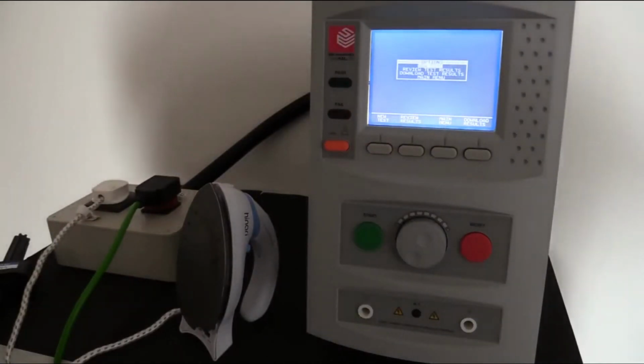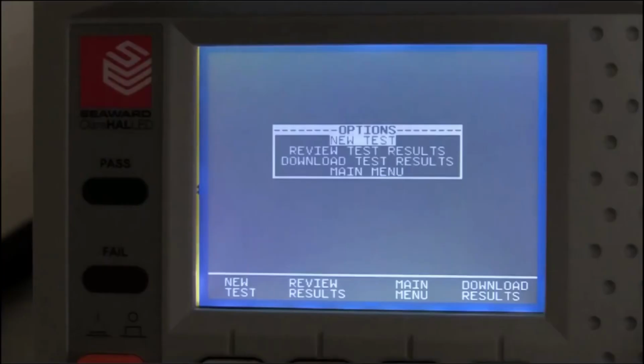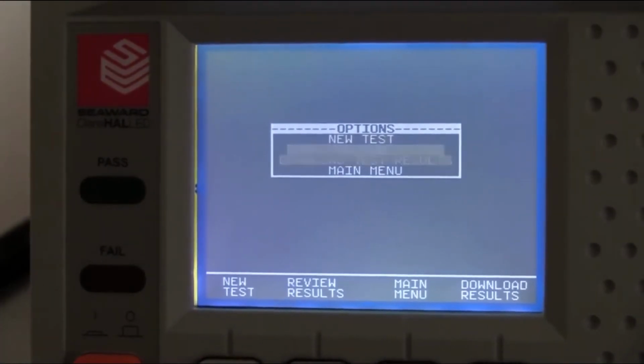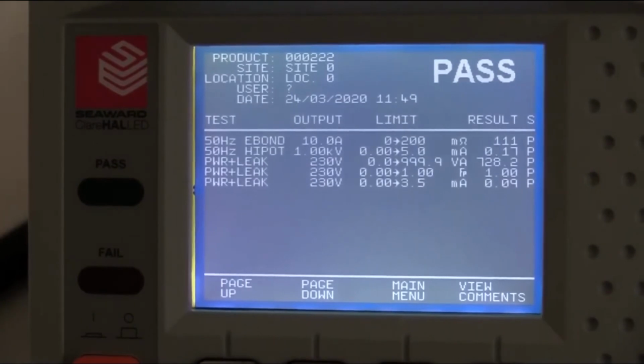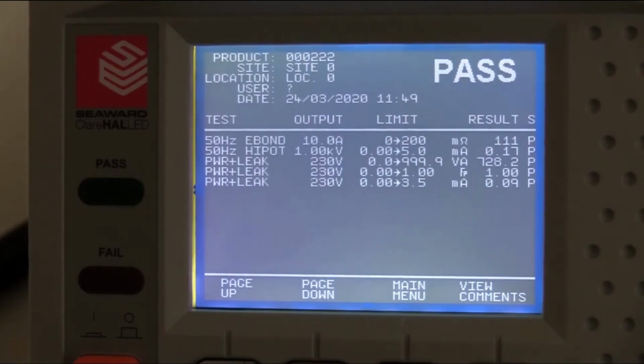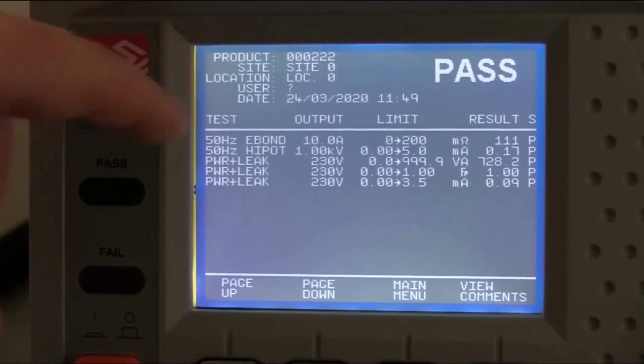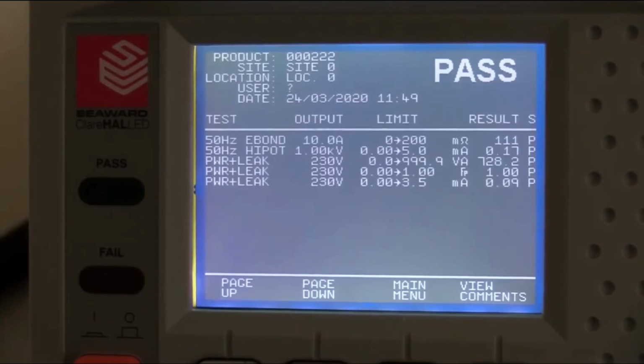The unit has passed, and in this case, we're set up to view a menu screen once the test is finished. So this menu screen allows me to demonstrate to you the kind of record that the HAL is actually storing. So we'll pick review test results, and you can see on screen now this is all the information that's stored within the HAL's memory regarding the test itself. So we can see the product, i.e. the serial number. If you do put things like sites, locations, or even users in, it will log all of that information. Date and time that the test took place, the overall result, pass or fail, and then we come into the actual measured values for each individual test.